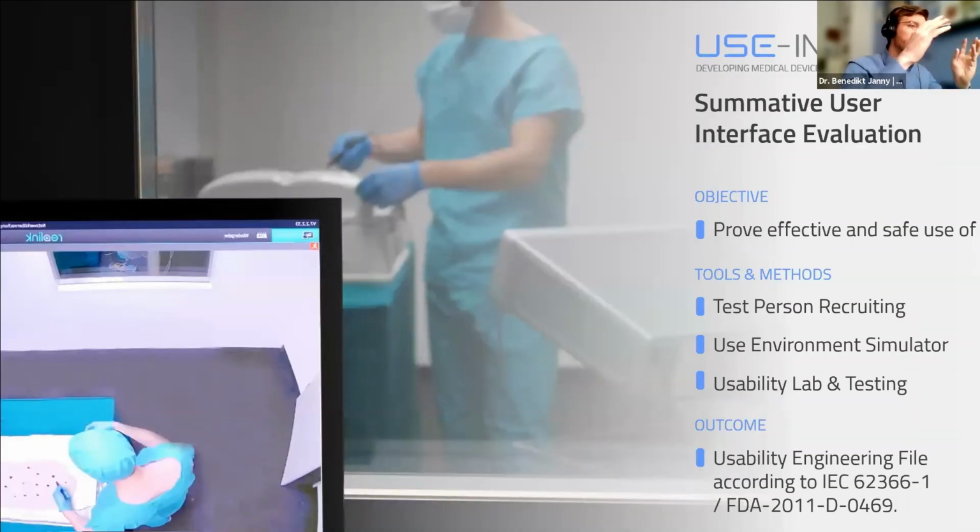And finally, if you're, as I said, happy with the product and all risks are controlled, you end up with the summative user interface evaluation. And the objective is to prove that your interfaces are effective and, of course, safe to use. The tools and methods that you need are a good test person recruiting. Keep that in mind, depending on where you want to release your medical device.